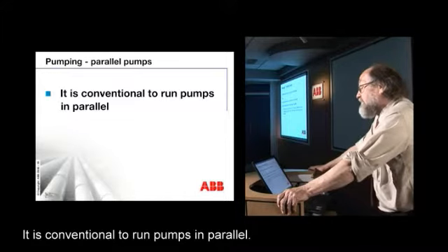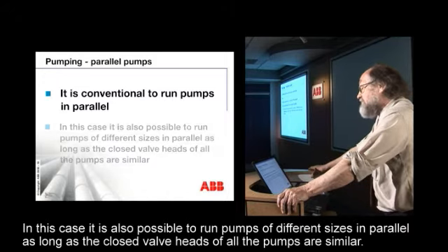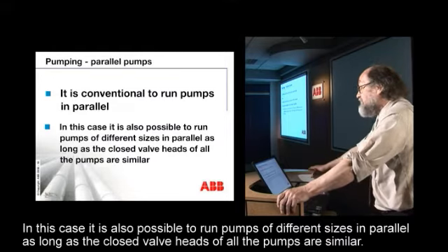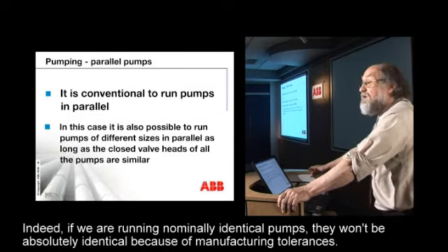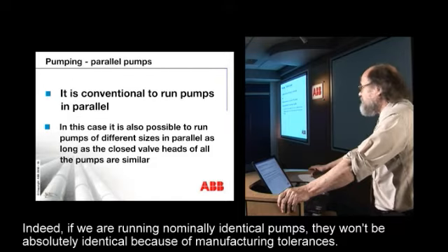It's conventional to run pumps in parallel. In this case, it's also possible to run pumps of different sizes in parallel, as long as the closed valve heads of all the pumps are similar. Indeed, if we're running nominally identical pumps, they won't be absolutely identical because of manufacturing tolerances.